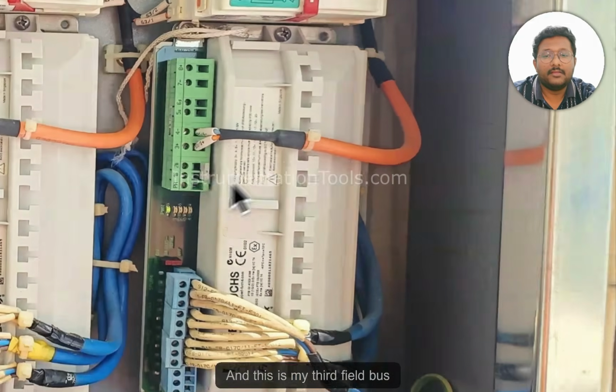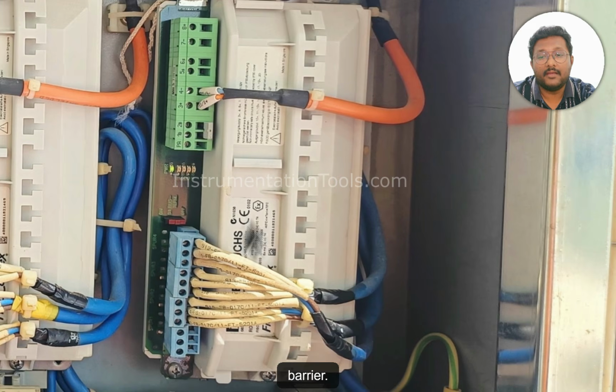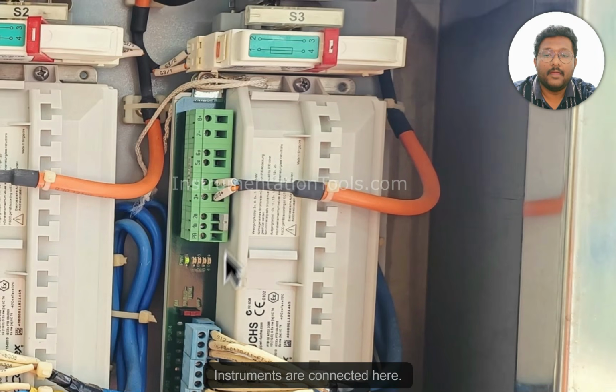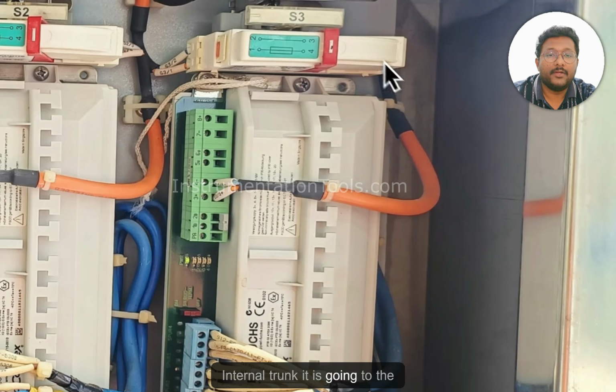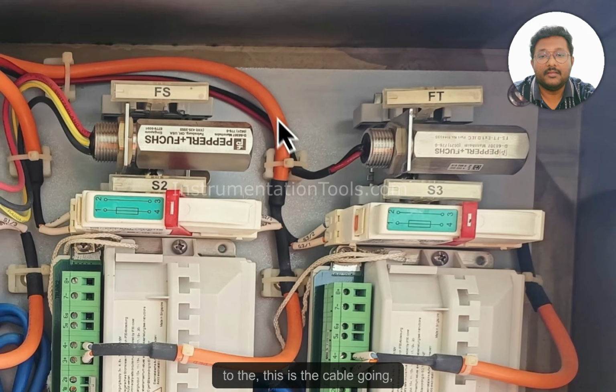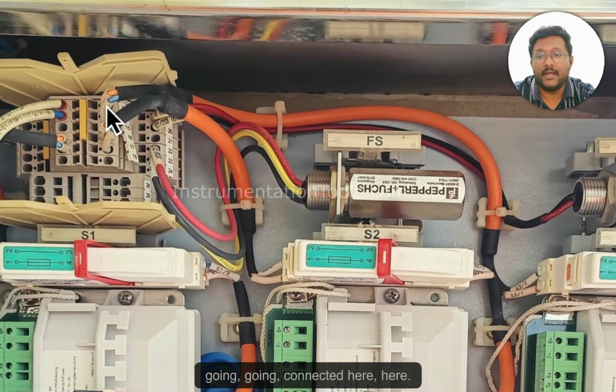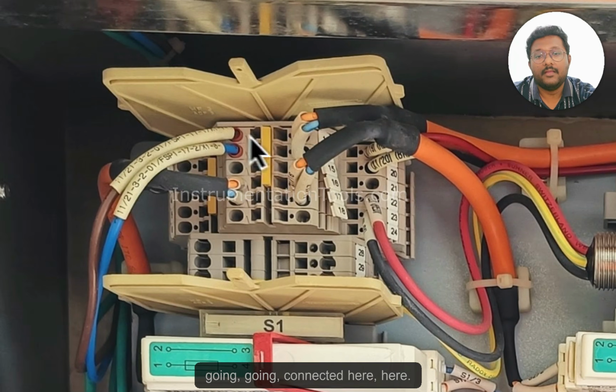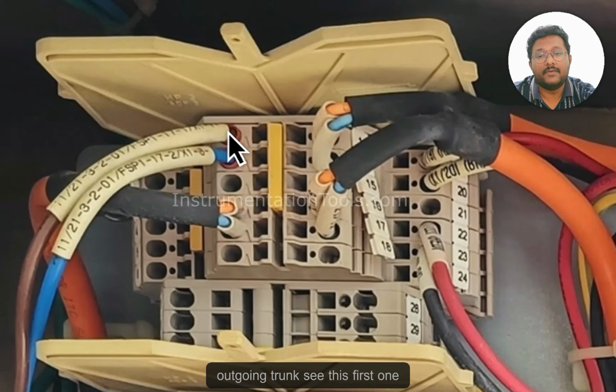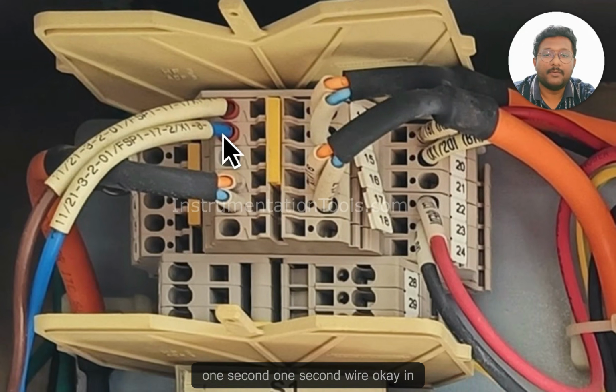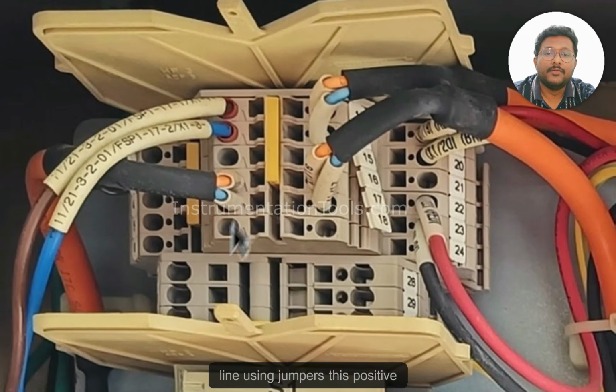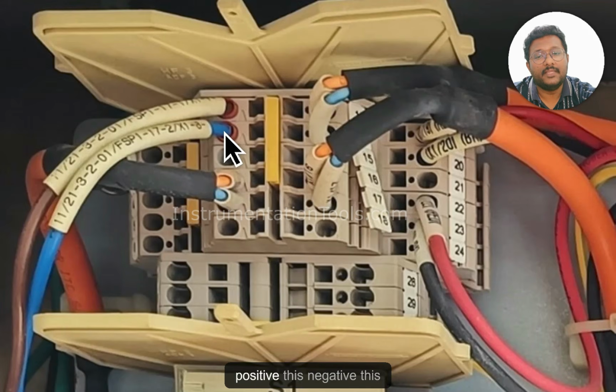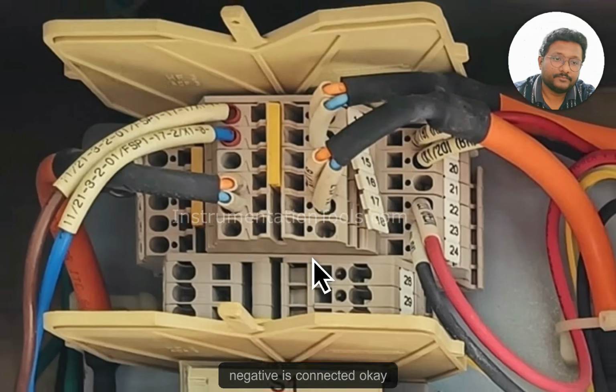And this is my third field bus barrier. Instruments are connected here. The internal trunk goes to the isolation switch, and this is the cable going and connected here. And this is my external trunk, the outgoing trunk. See, this first one and this first one are in line, the second wire is also in line. Using jumpers, this positive is connected to this positive, and this negative is connected.